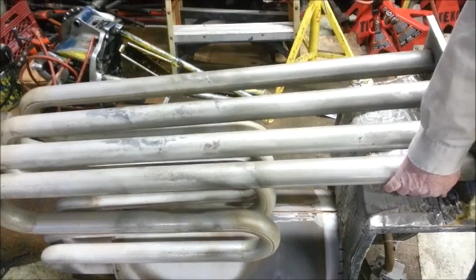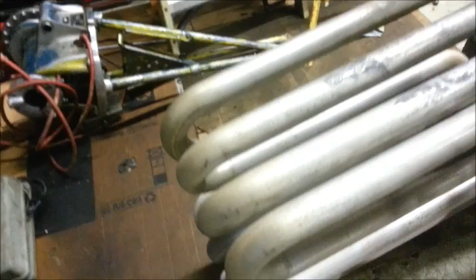Okay, the real action with a heat exchanger is occurring on the inside. Very little can be told from the outside because the outside is not subjected to adverse conditions. It's strictly the normal airstream going across it, nitrogen and oxygen with a little mix of the other stuff. But the combustion gases are quite acidic, and this is where the degradation takes place.